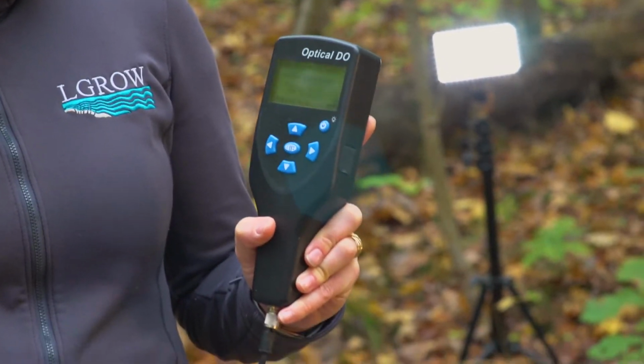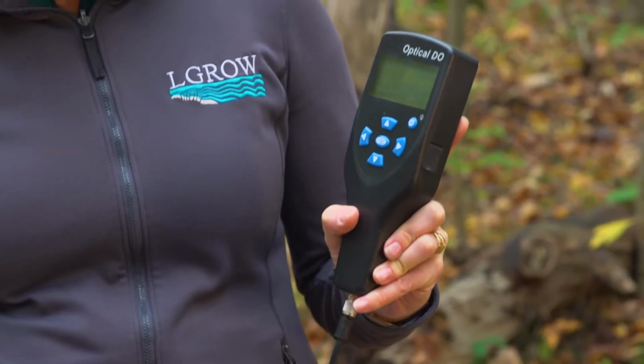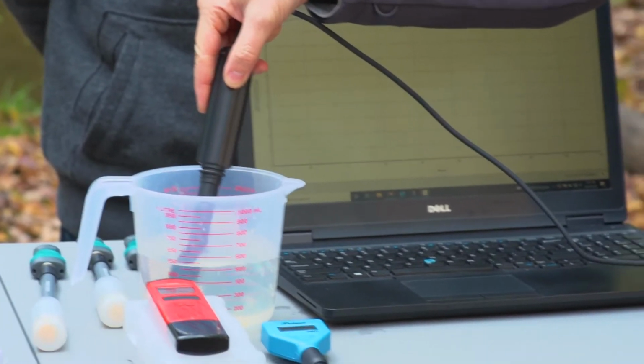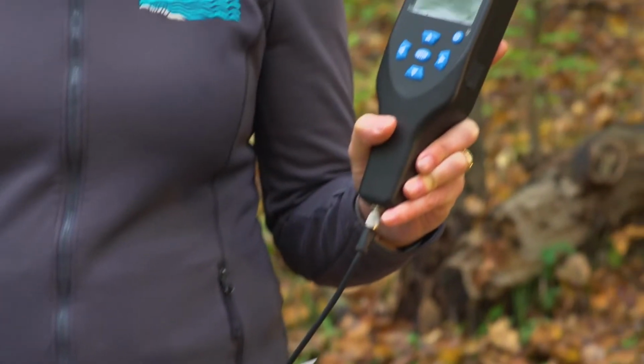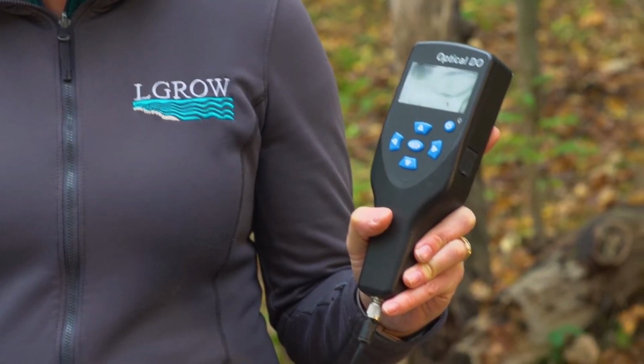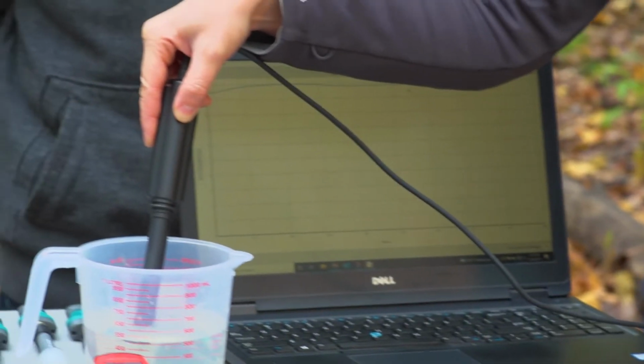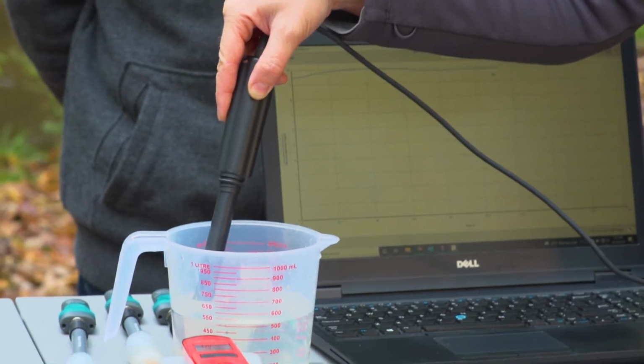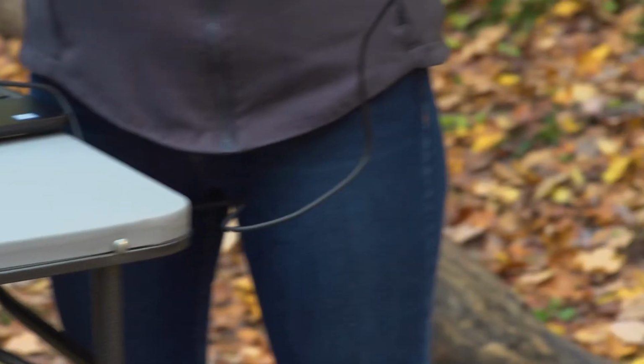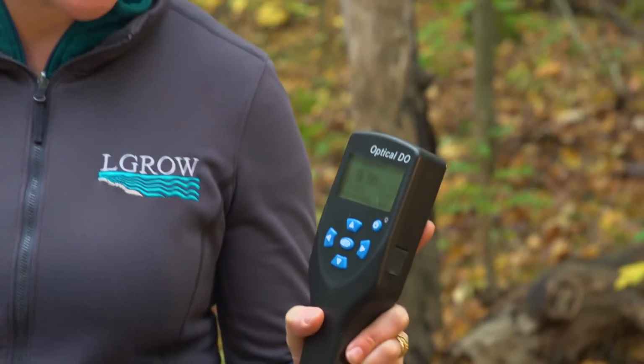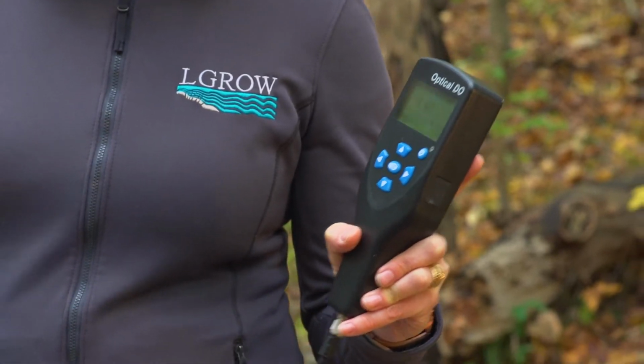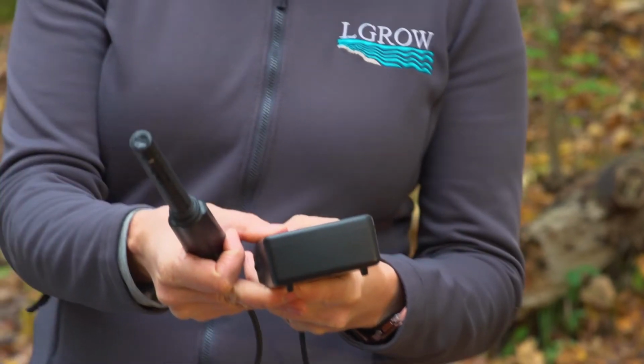So once it gets started up, you would set your probe into the water sample, and again, wait for the reading to stabilize. And again, it takes a few seconds. It's probably not going to stop at a certain number, but it will get to the point where it hovers around a certain area. And we're right around 9.9, which is right on track with our other samples that we took. So that's our dissolved oxygen reading.